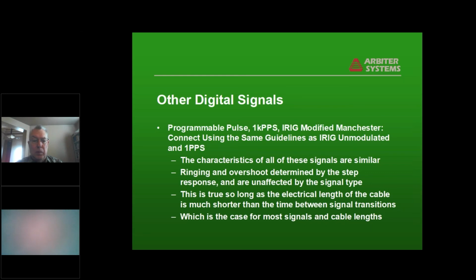Other digital signals, programmable pulse, 1,000 pulses a second, IRIG modified Manchester code, use the same requirements as IRIG unmodulated and 1 PPS because the critical characteristics of those signals are similar. They all have rise times on the order of 10 or 20 nanoseconds coming out of a clock. And the ringing and overshoot are determined by the step response of the system. By the time the next signal transition happens on all of those signals, all of that will have died out anyway because the electrical length of the cable is generally much shorter than the time between the signal transitions.